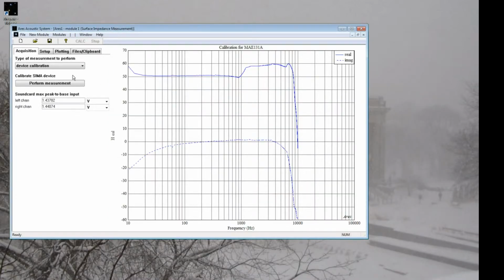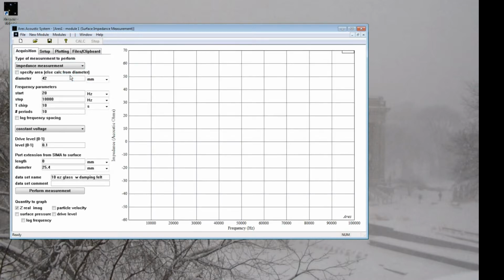Now that we've got a calibration curve, we can go ahead and do a measurement. So under Acquisitions, we want to select the type of measurement to be impedance measurement. I'm actually going to measure a glass jar, a small 10-ounce glass jar. It has an opening area of 42 millimeters. I've already got these parameters set up. I'm going to do as wide a frequency range as we can handle here, from 20 hertz to 10 kilohertz. I'm going to change the dataset name to be just 10-ounce glass jar. When we do the measurement, it's going to create a dataset, and it's going to give it that name, so we'll know what we took.